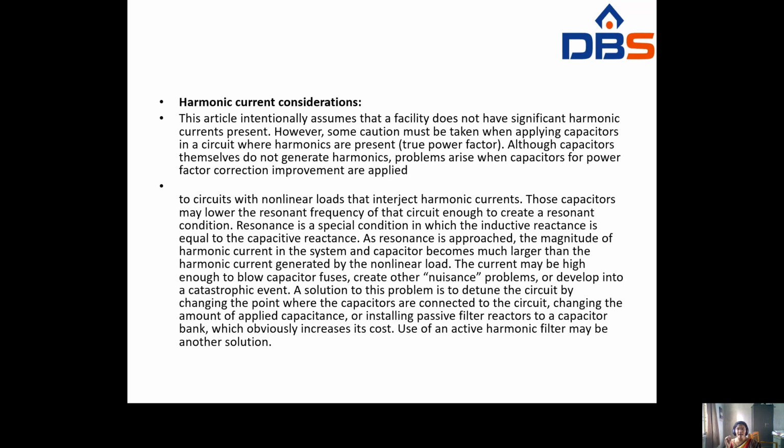So whenever we apply capacitors for power factor improvement to circuits with non-linear loads that inject harmonic currents, those capacitors may lower the resonant frequency of the circuit enough to create a resonant condition. Resonance is a special condition when the inductive reactance is equal to the capacitive reactance.